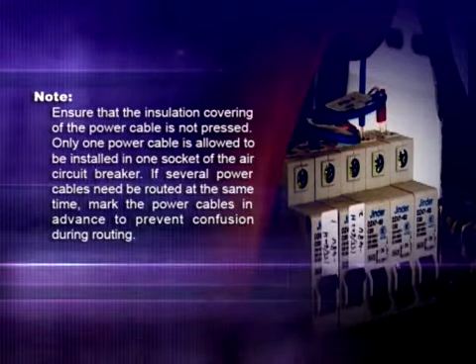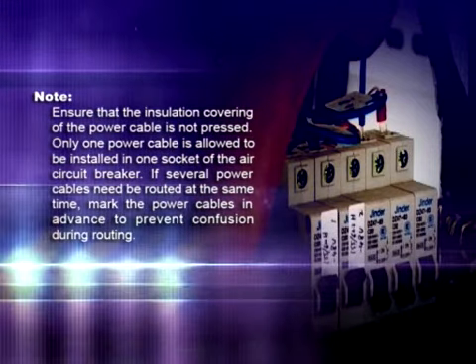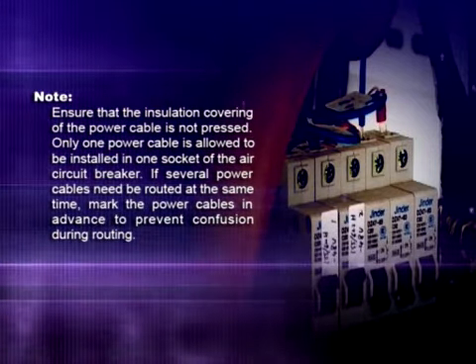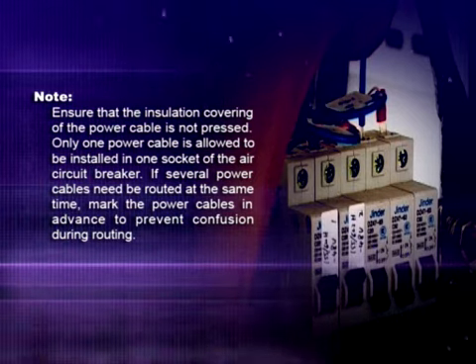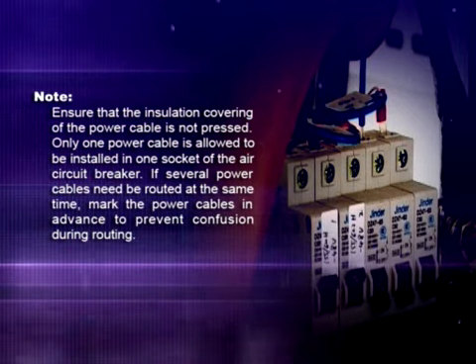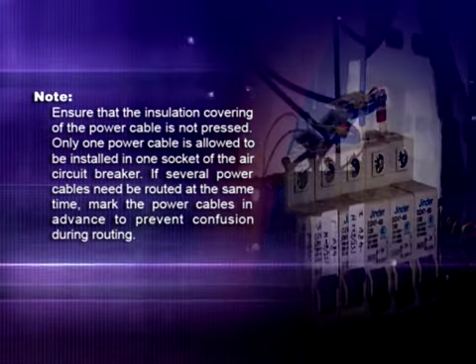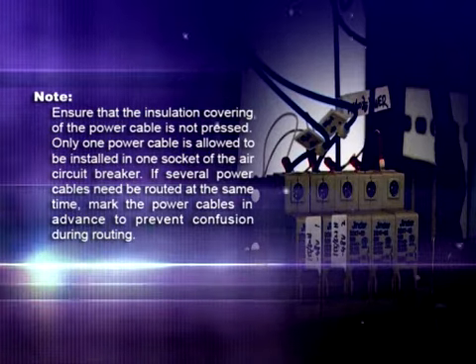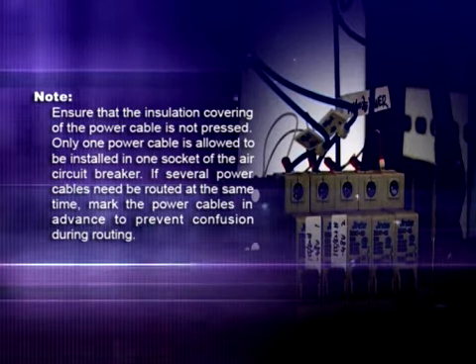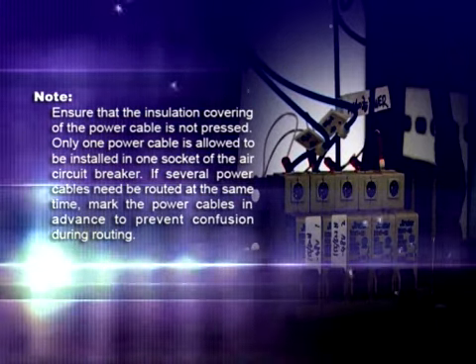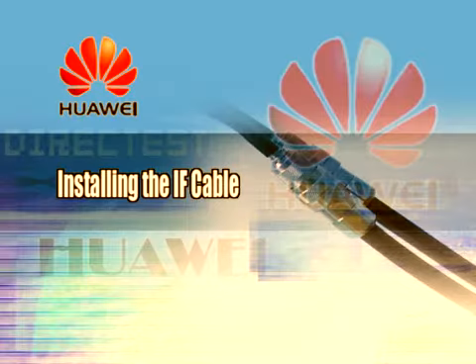Note: ensure that the insulation covering of the power cable is not pressed. Only one power cable is allowed to be installed in one socket of the air circuit breaker. If several power cables need to be routed at the same time, mark the power cables in advance to prevent confusion during routing. 4. Installing the IF cable.